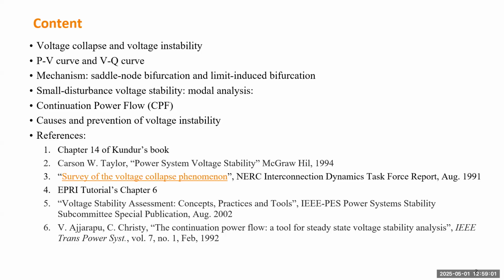So there are two types of issues. You may still recall there's one slide at the beginning of this class. I showed, starting from a very detailed model, including differential equations and algebraic equations, that we can study the nonlinear dynamics of the system. If you use a linearized model, that issue will be the small signal stability problem. If you only focus on the differential equations of the nonlinear system, even simplifying some equations to help you understand a transient stability problem, similar to a single machine infinite bus system. But if you only focus on how the operating point is moving until the system cannot sustain that operating point, you can use only algebraic equations based on power flow to study that problem. That falls into the voltage stability problem.